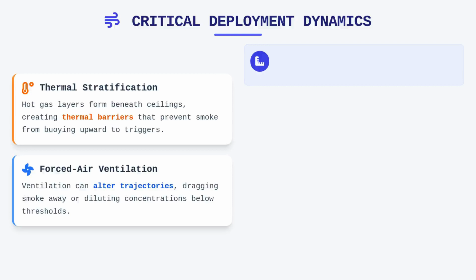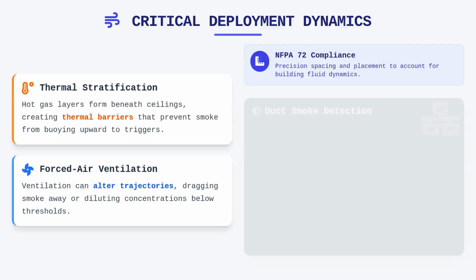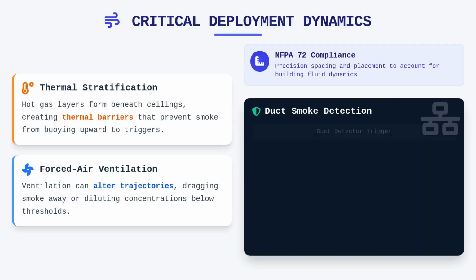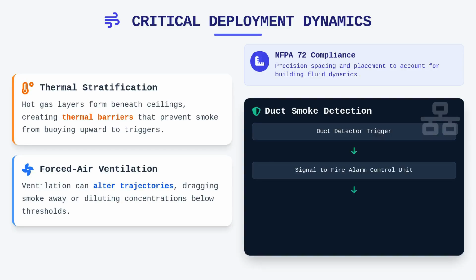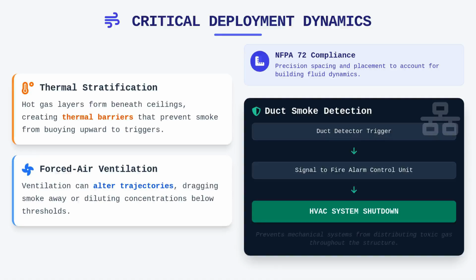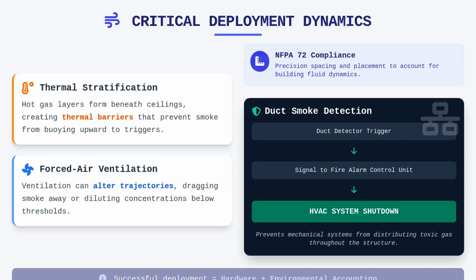We must design for these variables by carefully choosing detector spacing and placement according to NFPA 72 requirements. In ductwork, we utilize dedicated duct smoke detectors not necessarily to protect the building, but to provide a signal to the fire alarm control unit to initiate HVAC shutdown. This prevents the mechanical systems from acting as a distributed network for smoke and toxic gas throughout the entire structure.